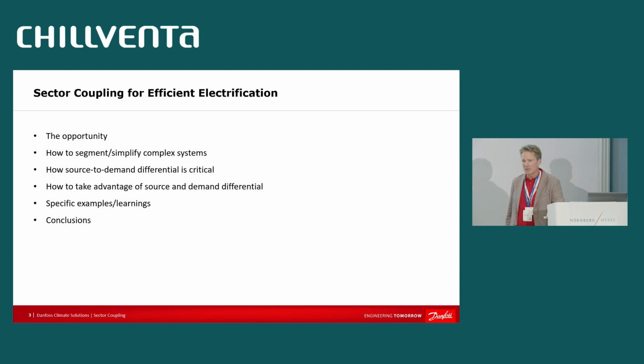Tuja touched on this, and so did Kim. But basically, the difference between a heating system of the past and a heating system of the future is that a boiler didn't care how much lift you were producing. If you're burning something, converting energy, whether you're producing 180 degrees C or 130 degrees C, it's basically the same efficiency. That completely changes when you talk about electrification and heat pumps.